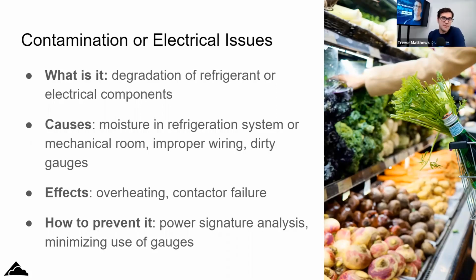Training. It's not even data, it's training. Data will help. But if you have a busted valve plate, you can do a few things to kind of tell it, but if it's on a rack, it's hard to tell. All the technician would have to do to get the customer up and running would be replacing that valve plate. Unless you put a sensor on every compressor, every discharge and every suction, maybe you'll be able to tell if it has a busted valve plate. And then there's still checks that you need to do. So it's complicated, but not as complex as it seems. So it's about going on site and running the tests in order to collect the right data, is what I'm hearing. Yeah. So you physically have to do stuff inside the compressor to see if it's that.